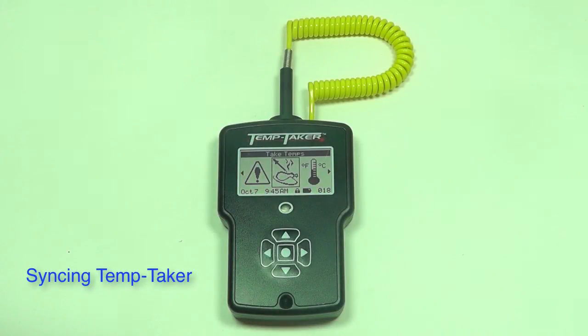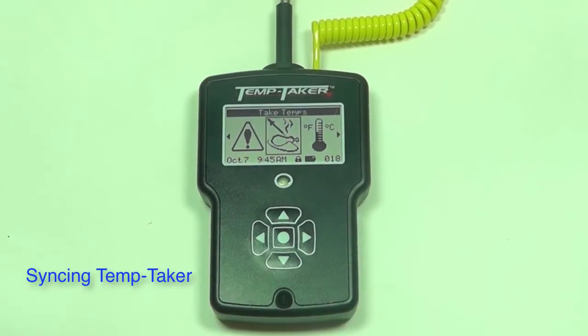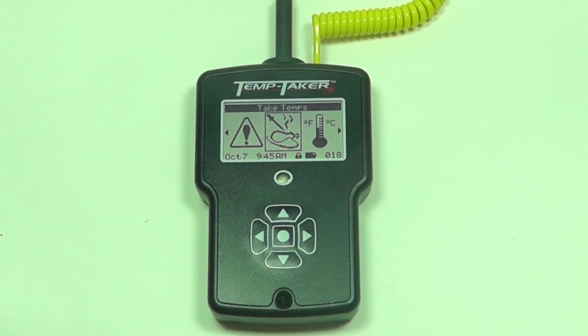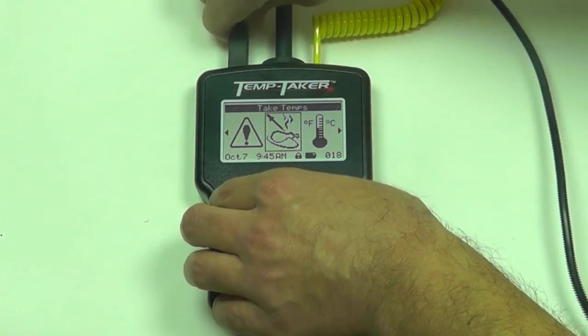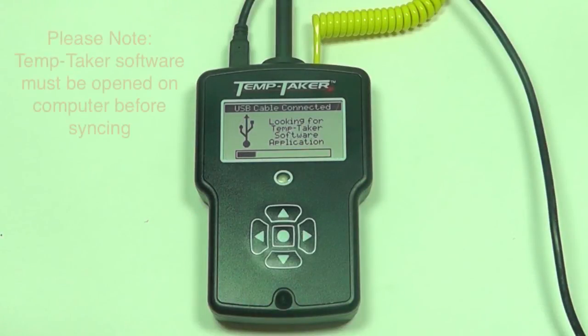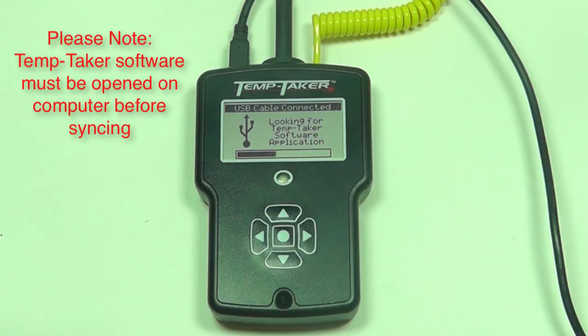Syncing the Temp Taker is a simple process. Under standard software settings, when you sync a Temp Taker to its software, the recorded data in the handheld is pushed into the Temp Taker computer program, and the memory of the handheld is then cleared. To sync the Temp Taker, simply plug in the provided USB cable into the computer that houses the Temp Taker software and connect the other end at the port at the top of the Temp Taker handheld. The only requirement here is that you need to make sure that the Temp Taker software program is opened on your computer. The sync process will happen automatically, and the screen will display a message saying everything was uploaded correctly when completed.